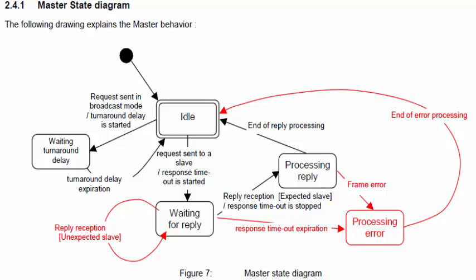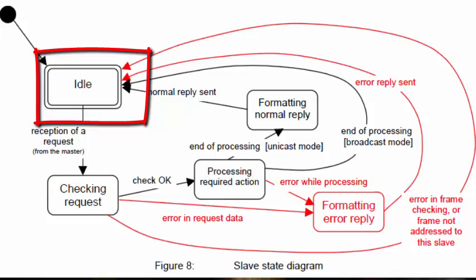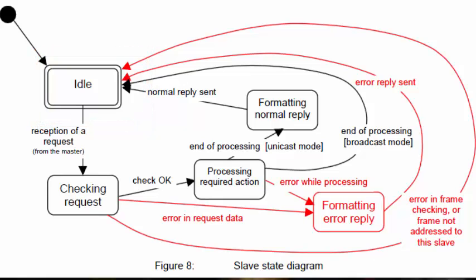The slave state diagram also contains an idle state. Unlike the master, the slave cannot leave this state unless it receives a request — it waits indefinitely until a request arrives from the master. The slave then checks the request: if the address field matches the slave's own address, the slave prepares and sends a response to the master, then returns to idle. If the request was a broadcast, the slave stores the broadcast value and returns to idle.